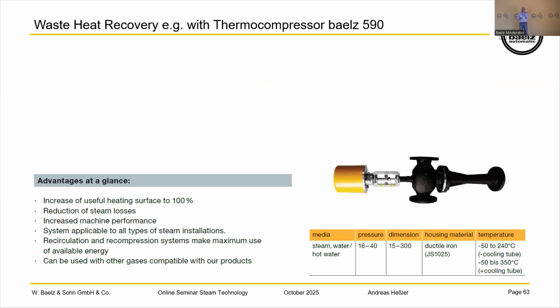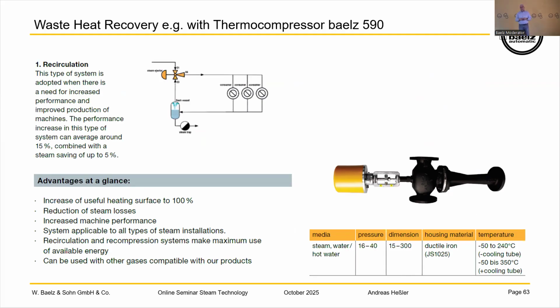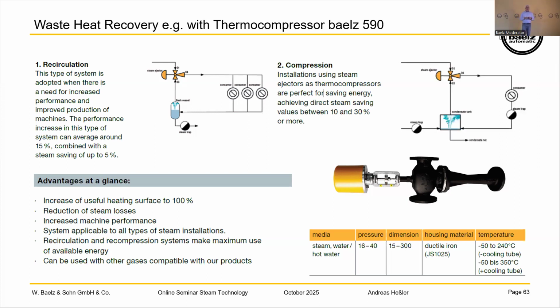Another solution from our side for steam water applications is our thermocompressor BAELZ 590, used for recirculation. Like the word says, recirculation: we have one circle where we can increase the pressure we have after the condensate flashing. And with compression, when we have an open vessel with some other condensate coming in, we increase the flash steam to a higher pressure level.